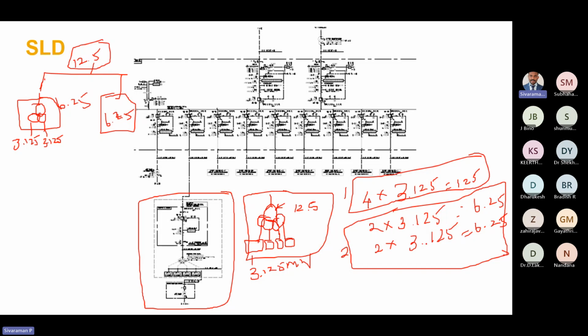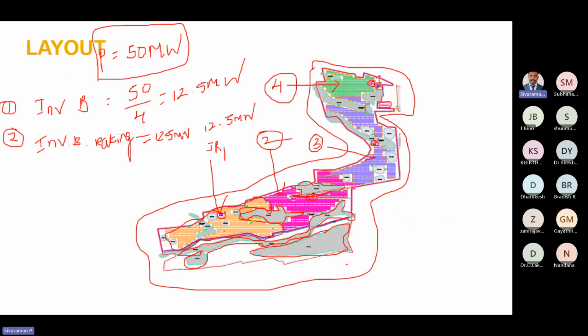To arrive at this configuration, whether we go with option one or option two, we have to do some technical commercial analysis. Which one is suitable for the particular location? There is no standard. We don't always have to follow four numbers of 3.125 megawatt to meet the requirement. It's not like that. It depends on the location. So the second one is the individual inverter rating.